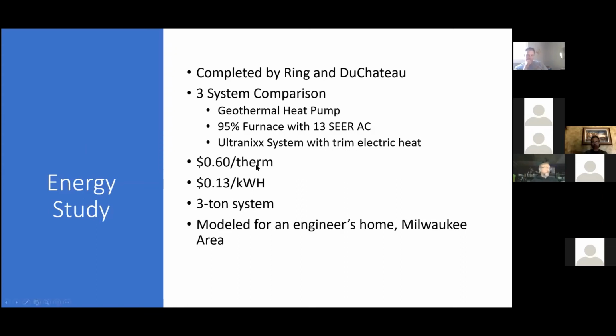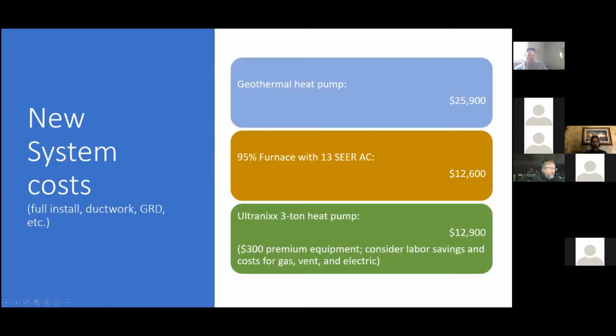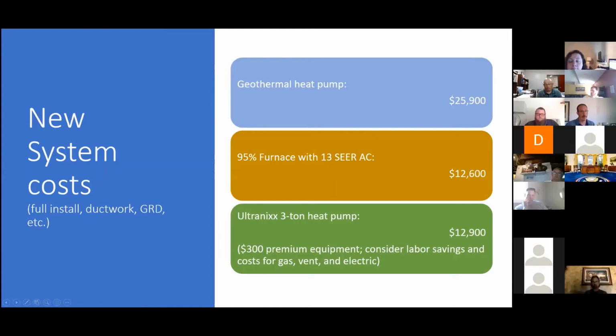So we didn't play around with the utility cost: 60 cents a therm, 13 cents a kilowatt hour. His home was 3 tons, and the home is in Milwaukee, and it's built. So on first costs, the geothermal heat pump is about double what the code compliant furnace and air-cooled air conditioner were. And then our Ultranixx, everything else is the same. This is a full install, so with ductwork. So there's a $300 spread. Maybe the $300 spread would be offset by not running gas or vent. Maybe it would go up a little bit for the electric consideration, but this difference is relatively inconsequential.